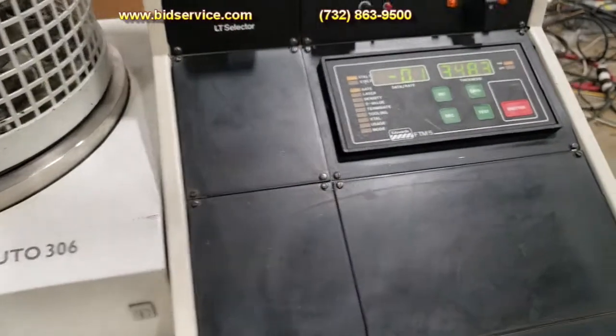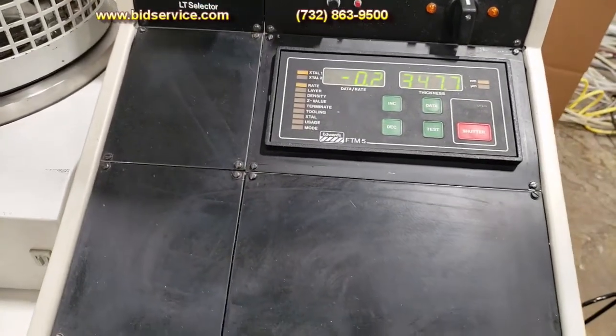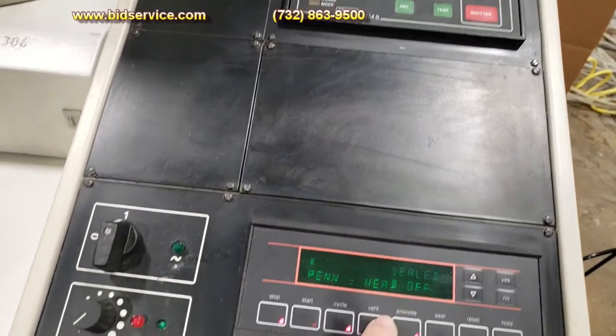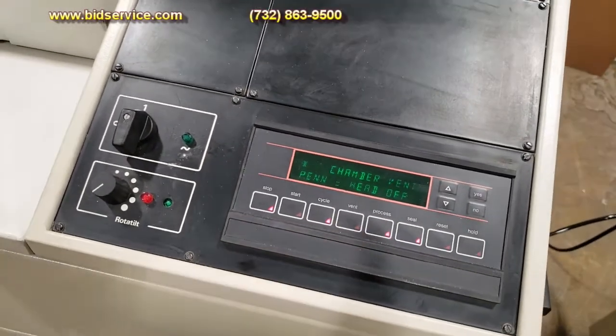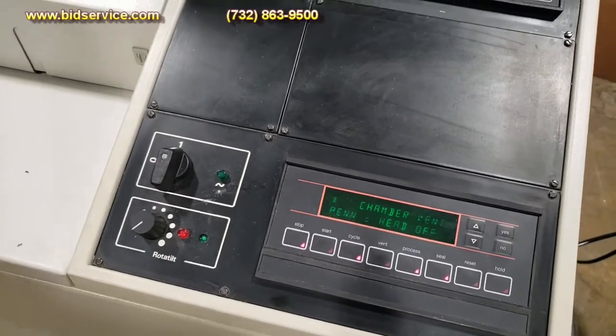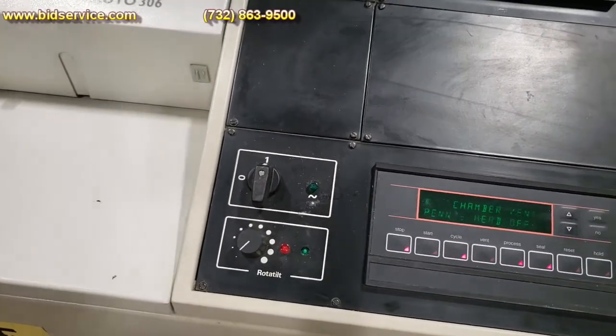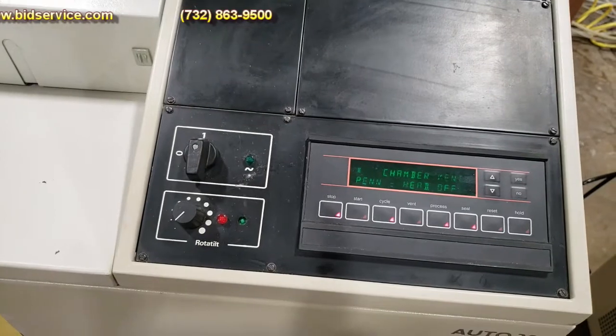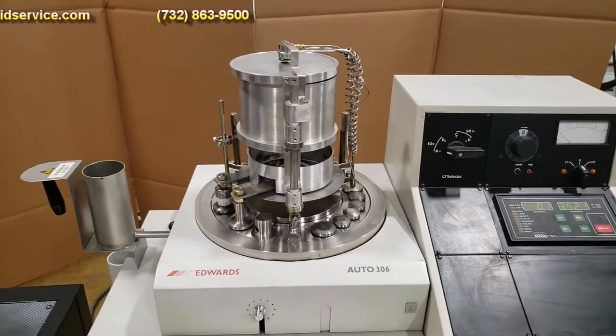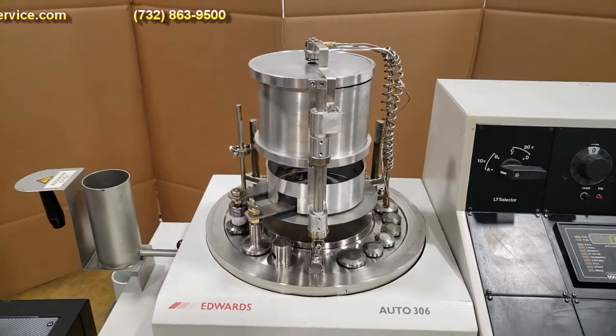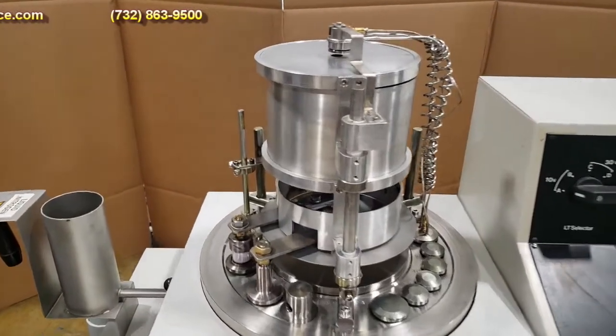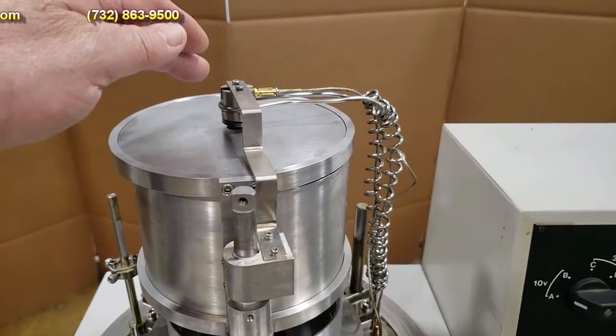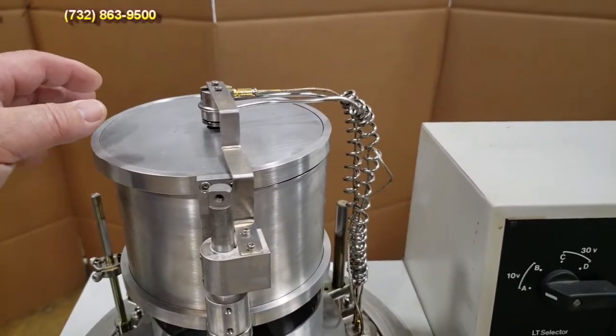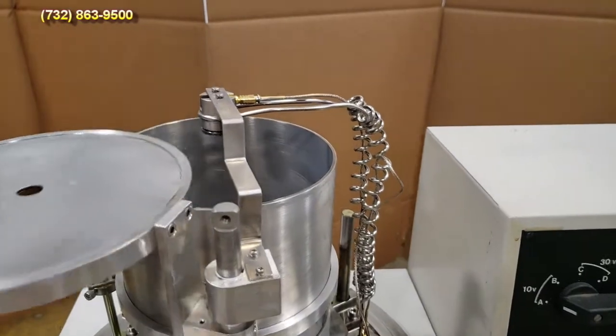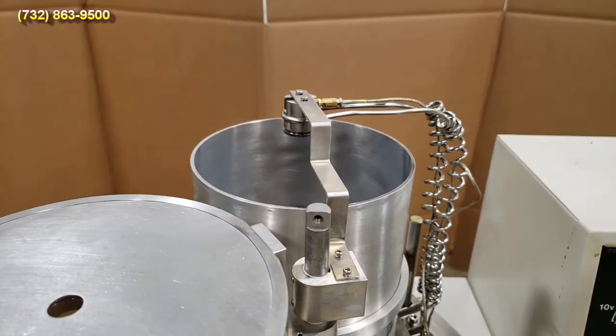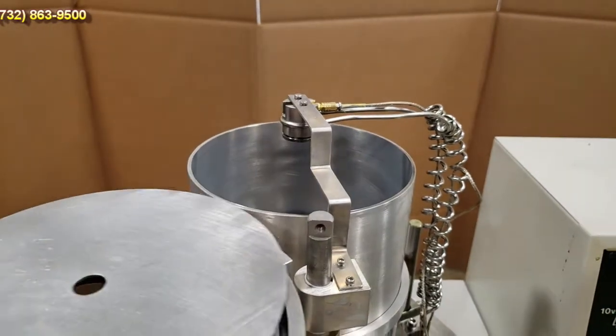Now what I'm going to do is hit this to vent the chamber, and we'll come back to open up the chamber and I'll show you the inside. Alright, so vented to atmosphere, and you have to manually remove the chamber, but in the chamber I'm going to show you, this is the deposition crystal. I can swing this over. This is your sample holder.